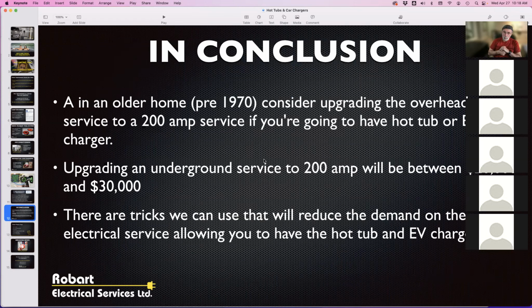In an older home, pre-70s, usually about '65, '66, there used to be a 60 amp electrical service. When I mentioned about looking at the end of the handle on your main breaker, a lot of the main panels pre-1965 did not have main breakers. Those were typically 60 and 70 amp rated electrical services.